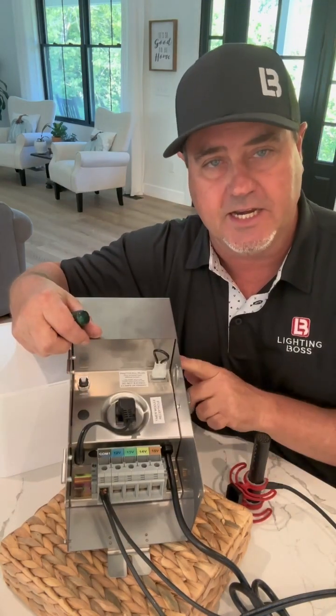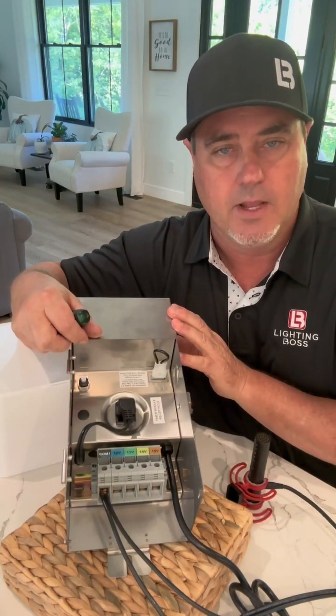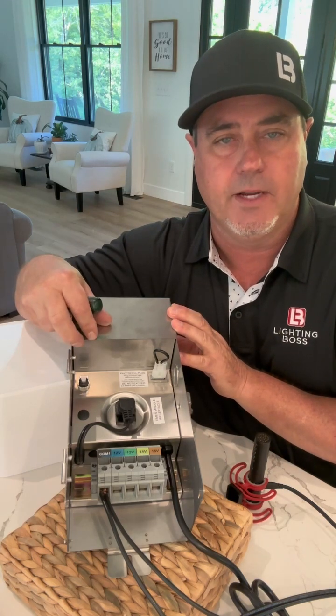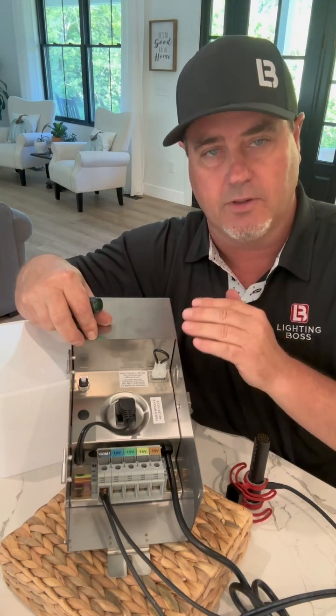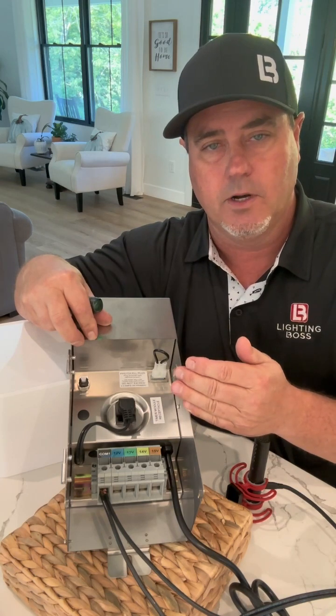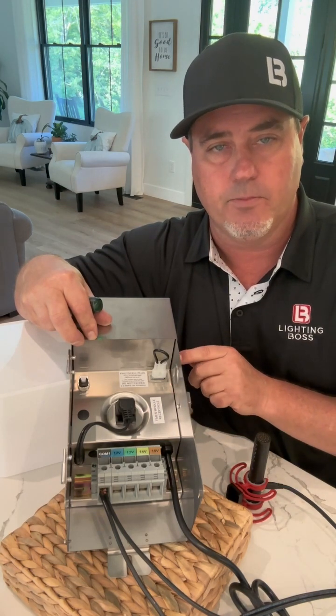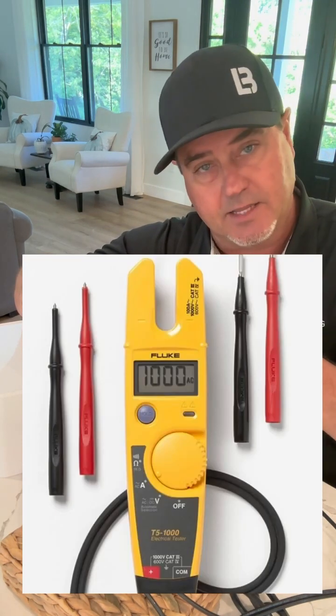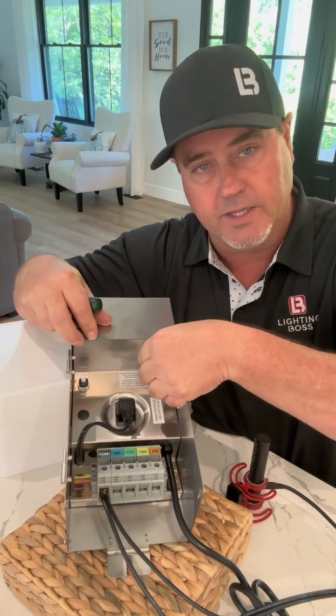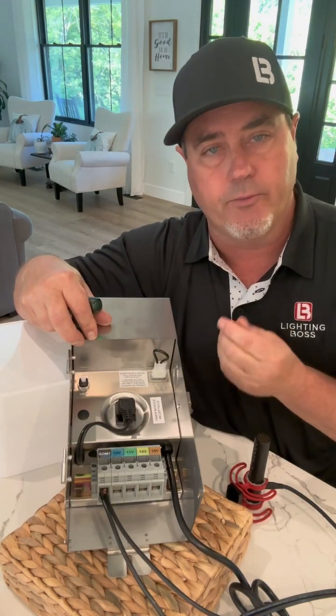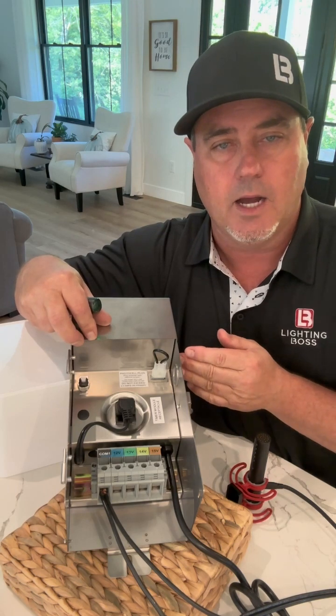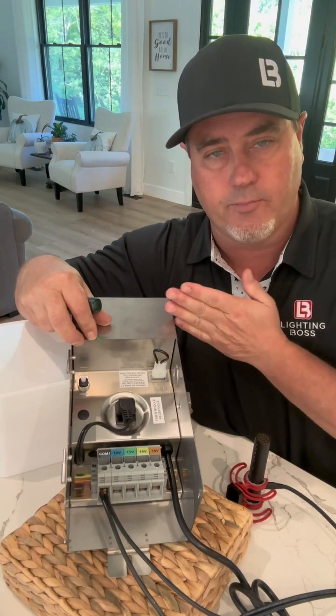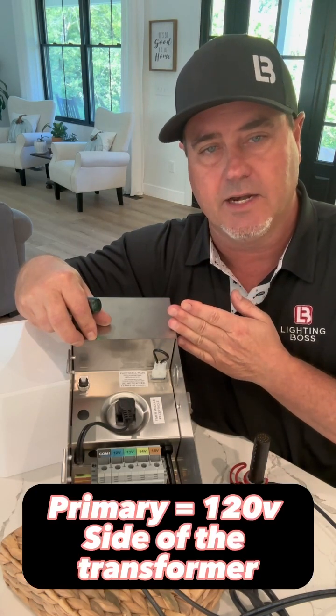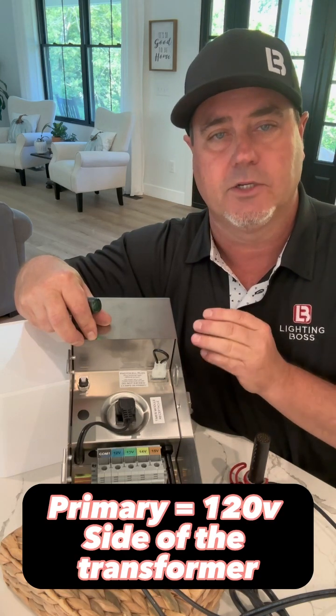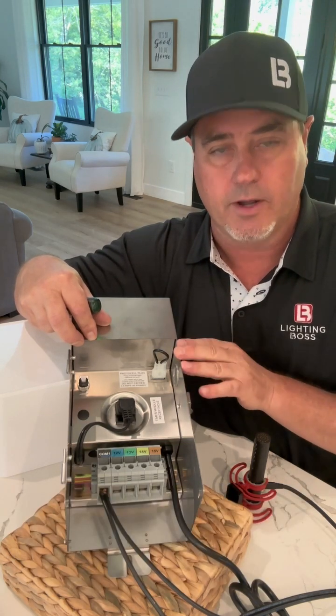When you're testing the transformer, once you get it loaded up with your lights and there's a load on the transformer, you can use your amp probe meter, take the claw piece and go around the actual loop here, and you'll get a reading. That reading is going to tell you on the primary side, which is the high voltage side, how many amps are actually being used with a load on it.